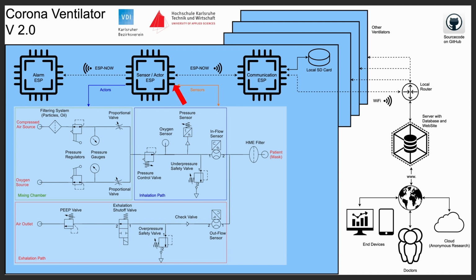Next on, the pressure control loop. The pressure after the mixing chamber is still too high for artificial respiration. In addition, ventilation should not only be an opening and closing of the air supply, it should rather be a closed loop control procedure.